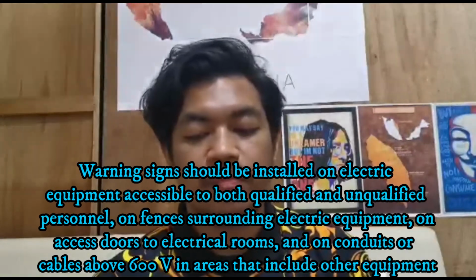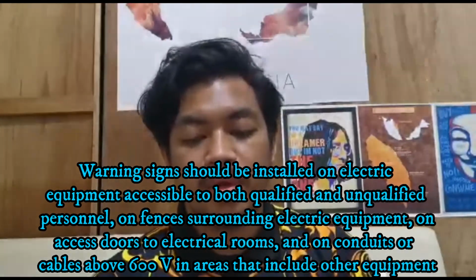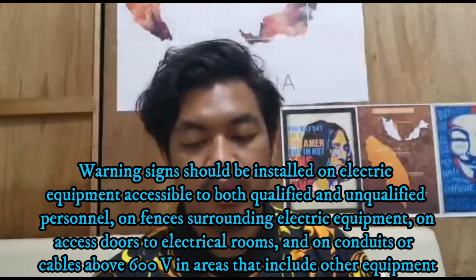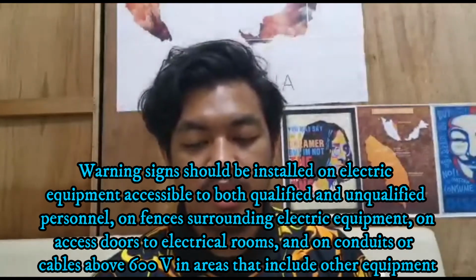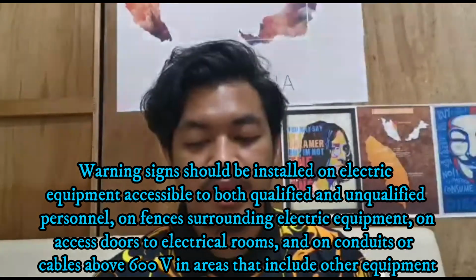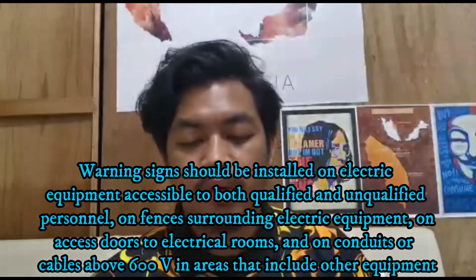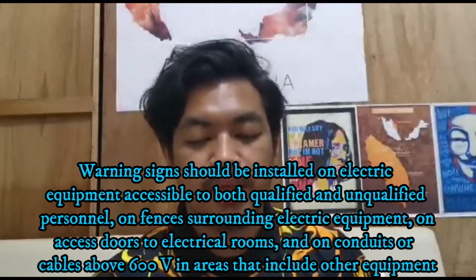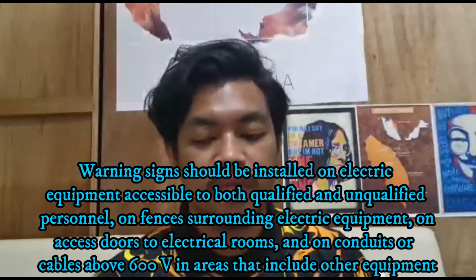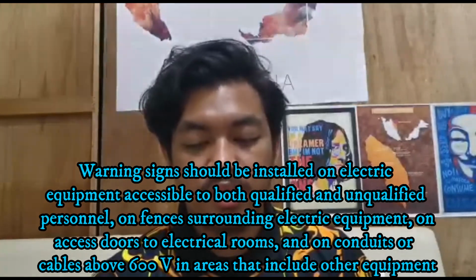Fourth, warning signs should be installed on electric equipment accessible to both qualified and unqualified personnel. The warning signs can be mounted on fences surrounding electric equipment, on access doors to the electrical room, and on conduits or cables above 600 volts in areas that include other equipment.